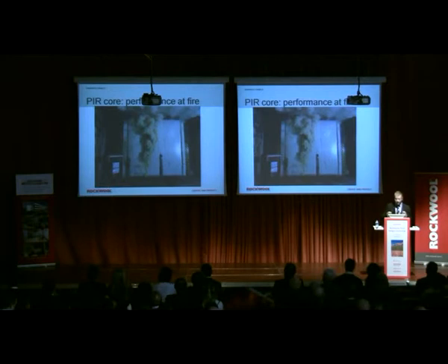If you look at this example, you can see what happens on the safe, unexposed side. After 4 minutes, we can see a significant development of gases. These gases are not coming from the furnace. These gases are coming from the construction, from the insulation infill. Can you see the clock now?